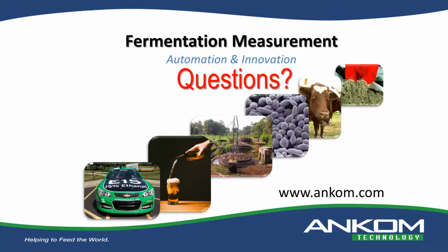I would suggest or mention, just as an aside to this, we have some people that are using an additional module, or maybe it's not a module, we call it the top hat, but we have a little insert that can go inside the bottle, under the module, if you will, to put something like sodium hydroxide in, which would absorb the CO2 and create a vacuum. And so it's a limited application, but some people are doing that in order to do BOD testing.